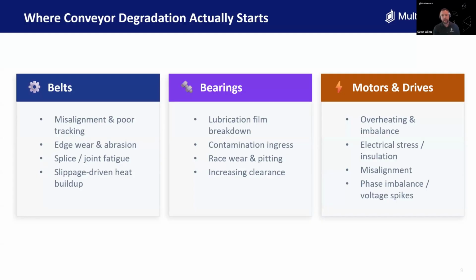Bearings, lubrication. Are they sealed for life? A lot of them are nowadays, but how quick does that break down? If it's not, are you lubricating with the right lubrication at the right time, with the right methods? Contamination ingress, that's something that we've seen a lot of. Pitting, false brinelling, race wear. I think bearings, we've seen a lot of issues with them.